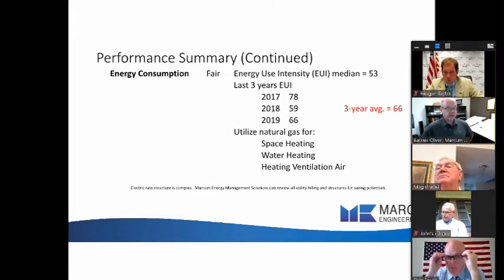We have a relatively new building. It should be doing better than this. It's a new building built with newer technologies and the better insulation that is required. So I feel like there are some energy savings that could be had, and I tried to structure a project to improve our EUI for the building. One thing I would recommend is that we consider using natural gas for space heating, water heating, and also for the ventilation air unit on the roof.